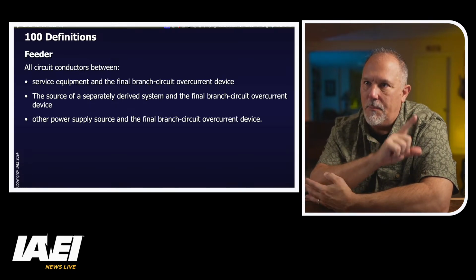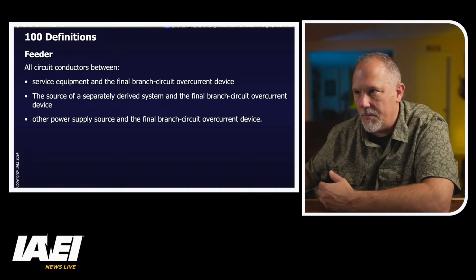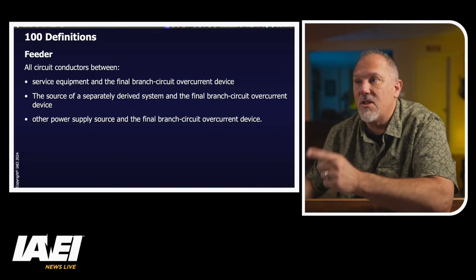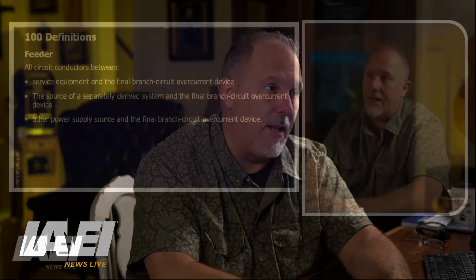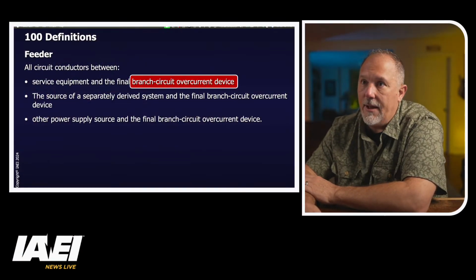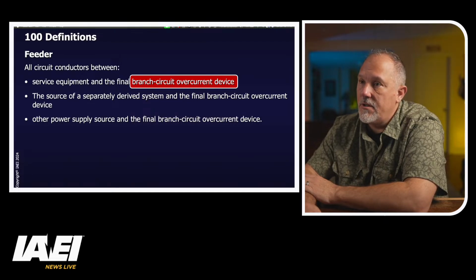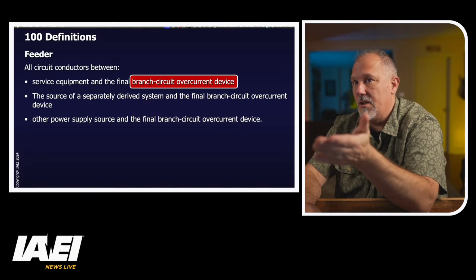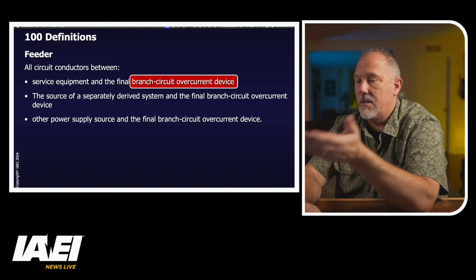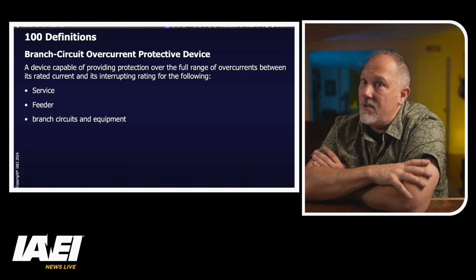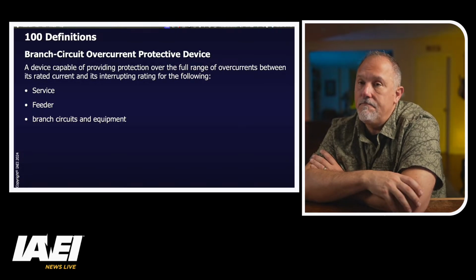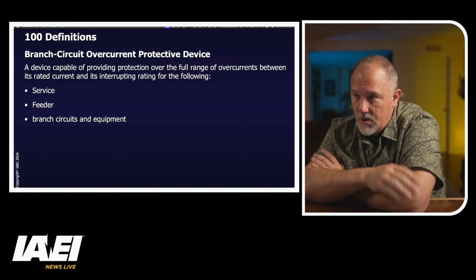Now, what I've had people say in the past is you have to have a branch circuit overcurrent protective device in the picture, and you do. But remember, it's not the overcurrent device that's protecting the branch circuit. Branch circuit overcurrent protective device is a defined term in the National Electrical Code. So let's take a look at what the branch circuit overcurrent device is. We shortened this one. We just call it a branch circuit overcurrent device. It's a branch circuit overcurrent protective device, and it is a defined term. Now, here's the issue. And we're fixing it in the 2026 code cycle.